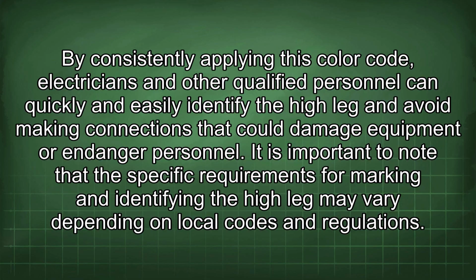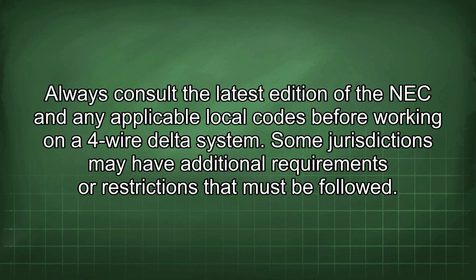By consistently applying this color code, electricians and other qualified personnel can quickly and easily identify the high leg and avoid making connections that could damage equipment or endanger personnel. It is important to note that the specific requirements for marking and identifying the high leg may vary depending on local codes and regulations. Always consult the latest edition of the NEC and any applicable local codes before working on a 4-wire delta system. Some jurisdictions may have additional requirements or restrictions that must be followed.